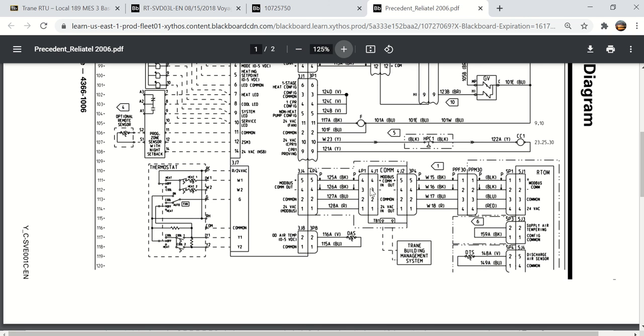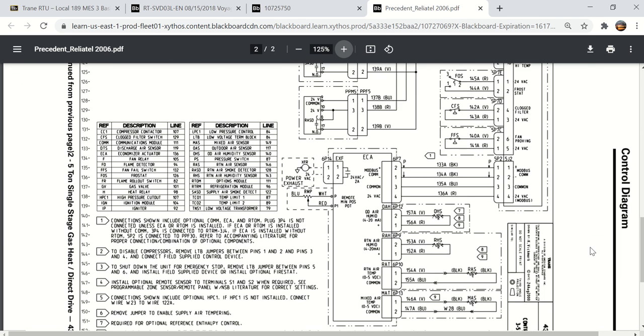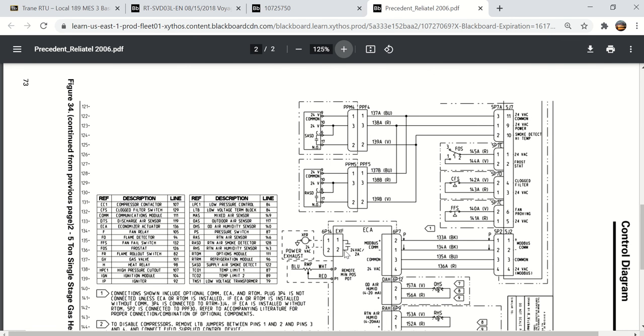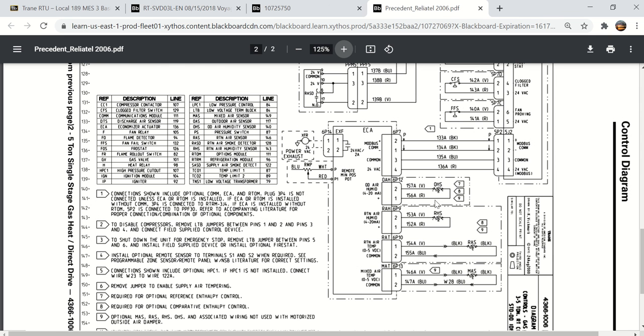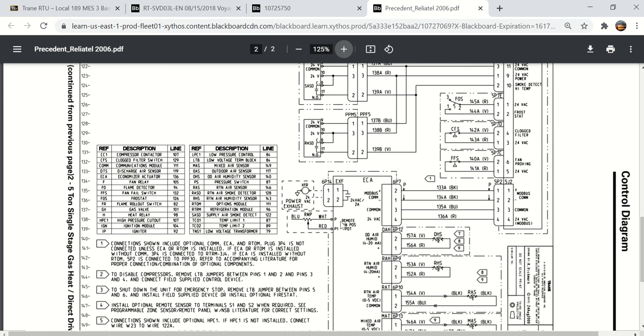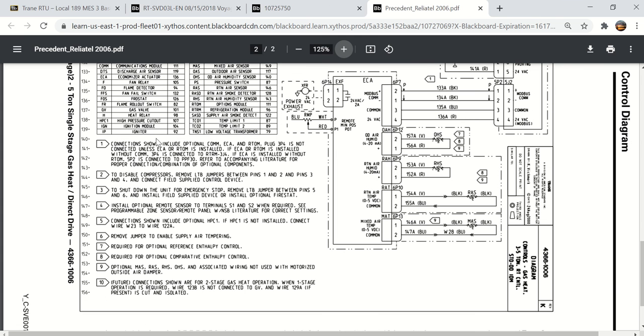Down here you see where there's a communications module that will go to a building management system. Here's the options board, the RTOM. At the bottom of the drawing, here is the economizer actuator. The economizer actuator has outdoor humidity, return air temperature, and mixed air temperature. That's how it does the enthalpy comparison if you're going to do outside to return, and control the economizer. Here is the relay output for the power exhaust. It's on the ECA board. Here's the legend for all the initials, and here's all the notes.